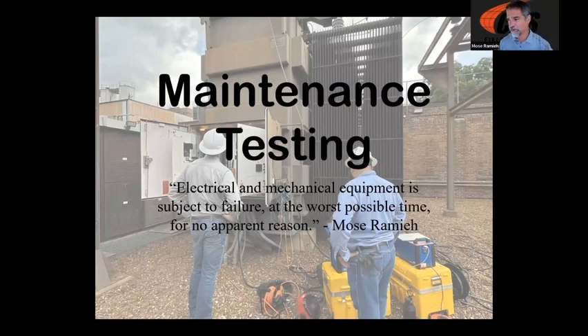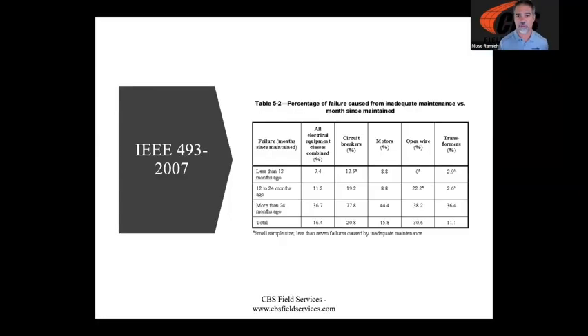Let's move on into some maintenance testing, and this is where I'll get into some of that new technology. I've been saying for years that anything electrical and mechanical is subject to failure at any possible time for no apparent reason, and maintenance tries to help us with that. There's an IEEE 493 that talks about how equipment left unmaintained will fail. And I'll just point this out: if equipment goes more than 24 months, we tend to have more problems with it. Probably no surprise there.